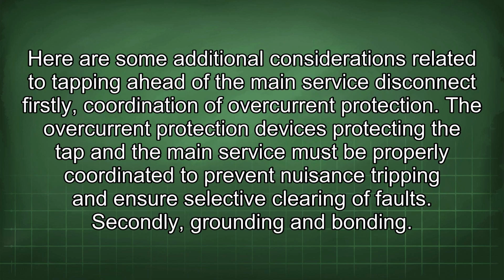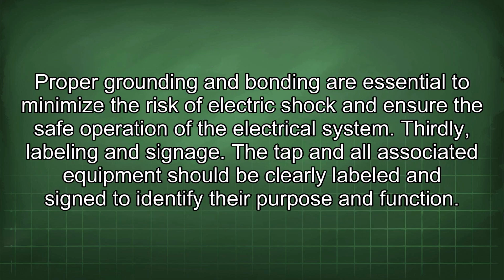Here are some additional considerations related to tapping ahead of the main service disconnect. Firstly, coordination of overcurrent protection. The overcurrent protection devices protecting the tap and the main service must be properly coordinated to prevent nuisance tripping and ensure selective clearing of faults. Secondly, grounding and bonding. Proper grounding and bonding are essential to minimize the risk of electric shock and ensure the safe operation of the electrical system.